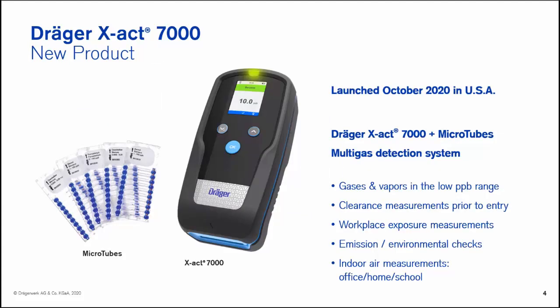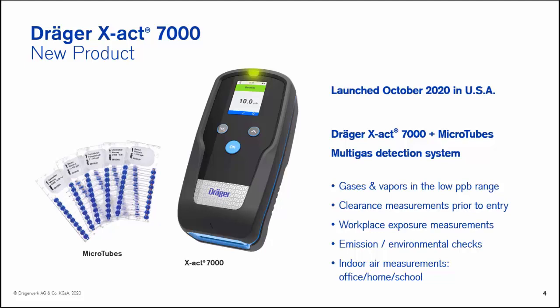With this first slide, the actual product consists of a two-component system, so you could liken it to a detector tube system of tubes and pumps. In this case, we have microtubes and the X-act 7000 device. The system is actually geared for multi-gas detection from the standpoint that we can do a multiple number of different analytes, so gases and vapors. One of the unique opportunities with this system is to capture very low concentrations, many in the low PPB range, for in particular some carcinogens such as benzene, 1,3-butadiene, formaldehyde, ethylene oxide, and also mercury.